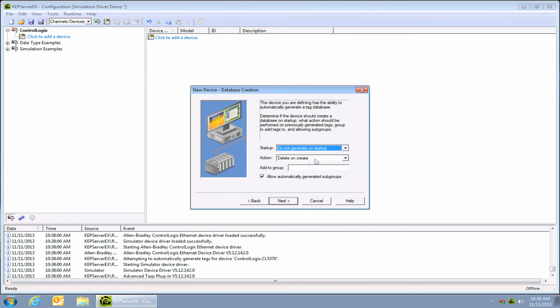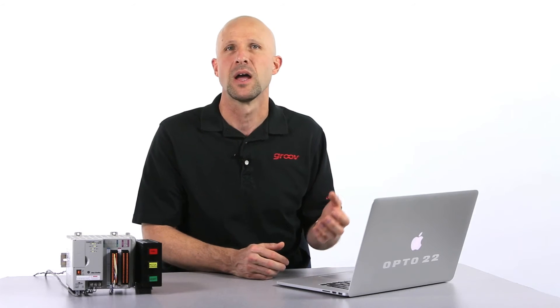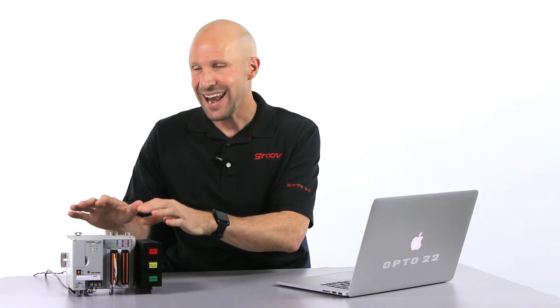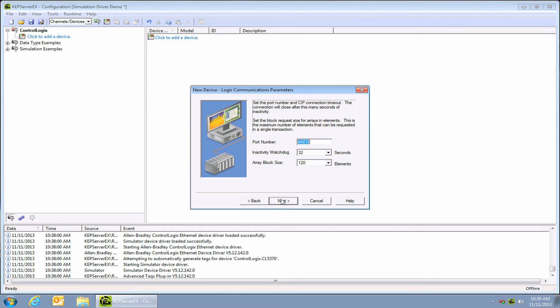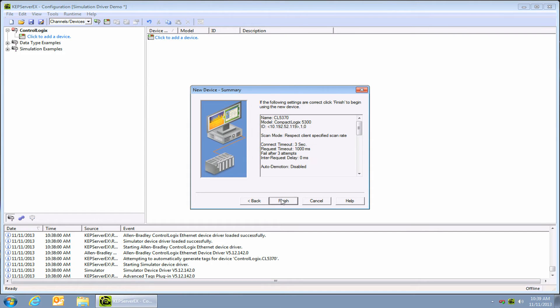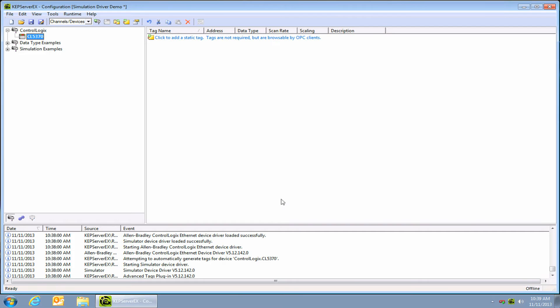Accept the defaults on the next few dialogues. But on this dialogue, let's have KepServer automatically create the tag database every time it starts up. That way, if I add any new tags to my AB device, I can add them to Groove without having to type them in manually. That's it — I'm done with step one. Now let's automatically import those tags into Groove.